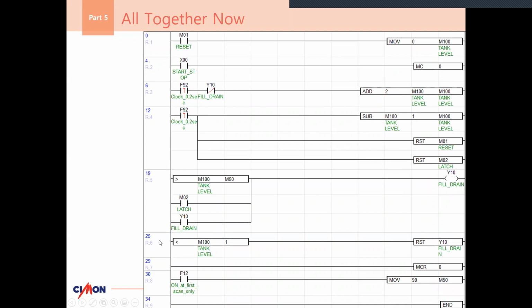I have parameters for when it will fill and drain by itself. When the tank level is greater than M50, it will activate Y10. Once Y10 is activated, this will no longer be turned off - it becomes a 1, and this will no longer add. So we'll just be subtracting 1 from the tank level every scan until we reach this parameter. When it has reached less than 1, it will reset Y10, and therefore I'll be adding 2 again, so we'll be adding 1 to the tank level every scan.